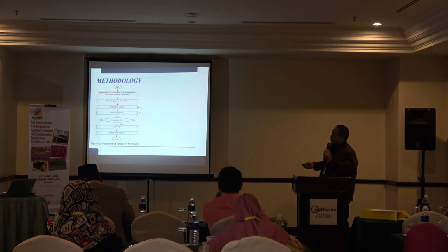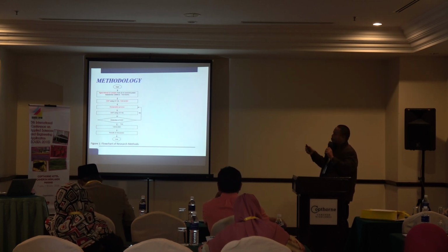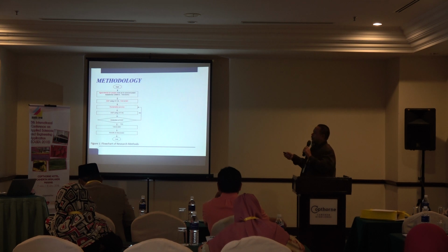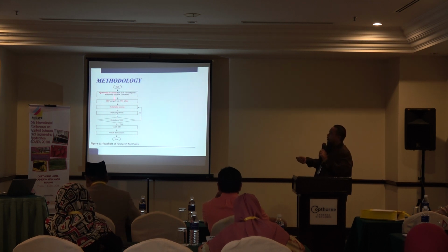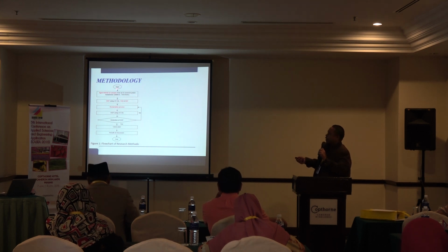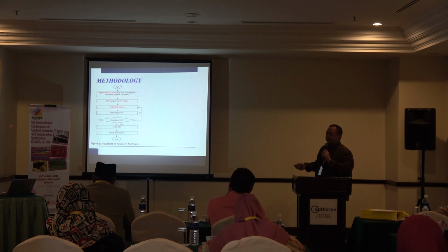So in this project review, we are trying to prove whether it can be done or not by using fuller earth. Our mineral oil samples are taken from in-service power transformer oil, which we get from the MB distribution. Then we use UV-Vis as a method to know the dissolved decay products inside the oil. We do the total acid number, then the breakdown voltage or dielectric strength of the oil, do the reclamation process, and see what happens after.